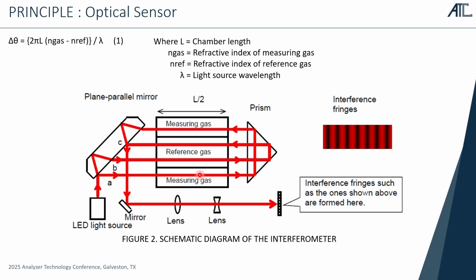And then this interference fringe moves in proportion to the difference of refractive index between the measuring gas and the reference gas. So simply say, if a high BTU gas comes into the sensor, this interference fringe moves from left to right. So higher BTU value, more movement. So this is how the optical sensor works.